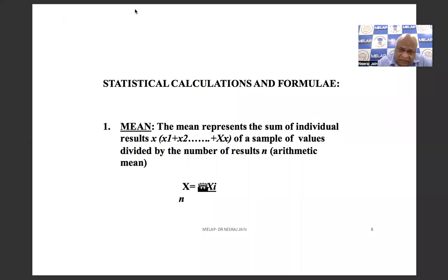Now, you please write in the chat box, which mean is more useful? Mean which you are calculating in your lab, or mean which is provided to you by the manufacturer? Which mean is more useful? Okay, lab mean. Yes, Akriti, why lab mean is better? Because it is calculated based on our values. Yes. Usually we use the manufacturer mean, then we create a lab mean from a set of, like, 20 data points or 40 data points. So it's better.